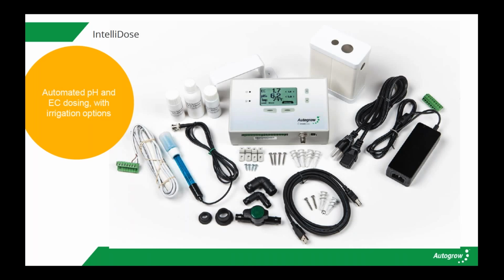So what you're looking at here is the IntelliDose controller, and this is the whole kit. As you see, it has an EC and a pH probe that it comes with, so it's monitoring EC, pH, and the temperature of the water. On the top right, that little plastic pot is what we call the sample pot, and that holds the EC and the pH probe to make sure that they stay safe, that they always have a good sample of what's happening in the reservoir on them. It makes them really easy to get to and calibrate. So this is the hardware for the IntelliDose.